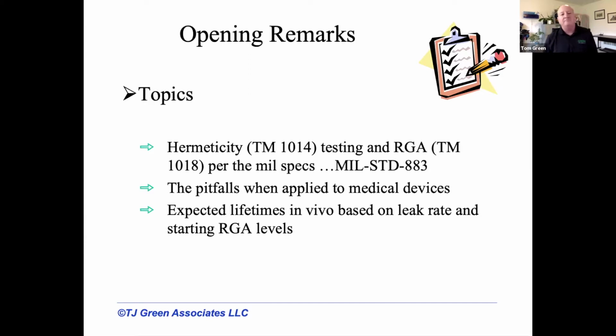For starters, the operational environment's not quite the same. Instead of minus 55 to 125 C, you're working at basically 37 C body temperature. And device lifetimes and things like that are a little different. So I'm going to touch on some of those pitfalls. And then towards the end of the talk, I'll walk you through how you can make a projection of how much moisture you would expect in the device for a given leak rate and a given starting residual gas moisture level at time 0. So we'll get into all that in a minute.